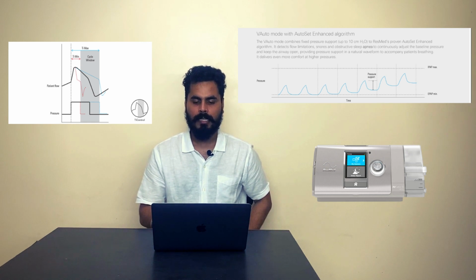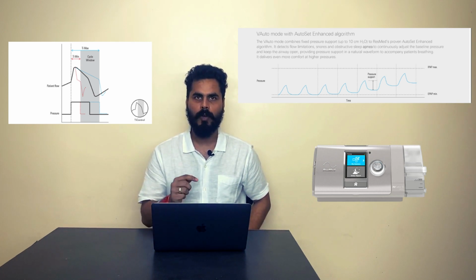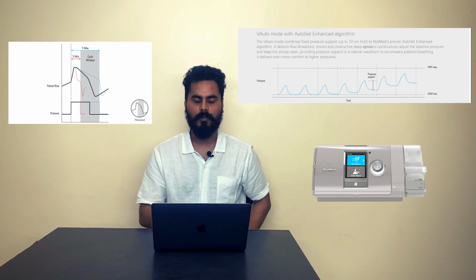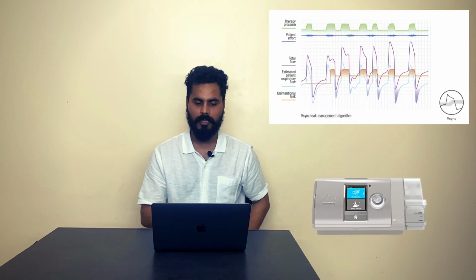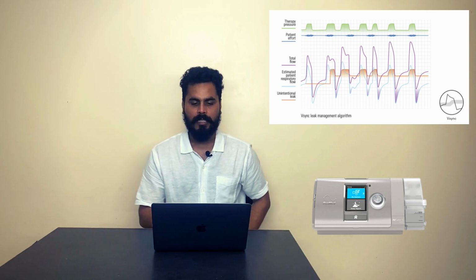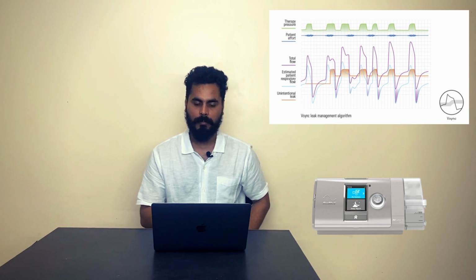What it does is sense the breathing pattern of the user and adjust the rise time accordingly. Rise time is the shift from EPAP to IPAP. Easy Breathe does it automatically for the patient. You don't have to set a manual value for it. Then there is a V-Sync algorithm which ensures patient and ventilator synchrony in case of leakage through the mask while using the VAuto machine. This feature is very important for effective therapy.